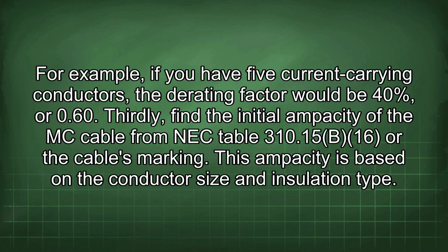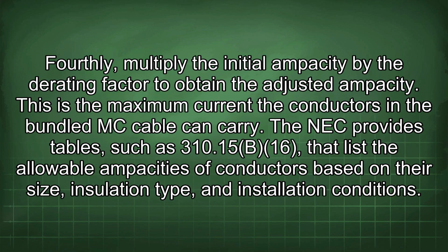Thirdly, find the initial ampacity of the MC cable from NEC table 310.15(B)(16) or the cable's marking. This ampacity is based on the conductor size and insulation type. Fourthly, multiply the initial ampacity by the derating factor to obtain the adjusted ampacity. This is the maximum current the conductors in the bundled MC cable can carry.